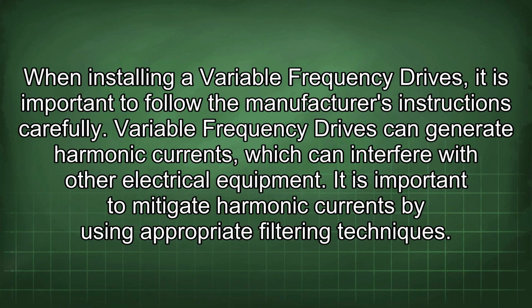When installing a variable frequency drive, it is important to follow the manufacturer's instructions carefully. Variable frequency drives can generate harmonic currents, which can interfere with other electrical equipment. It is important to mitigate harmonic currents by using appropriate filtering techniques.